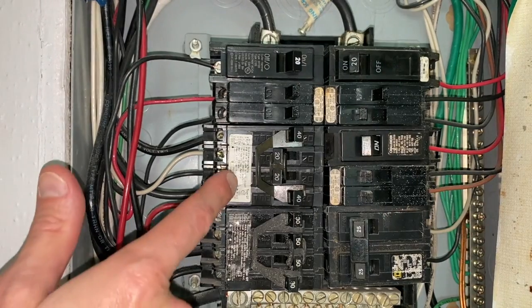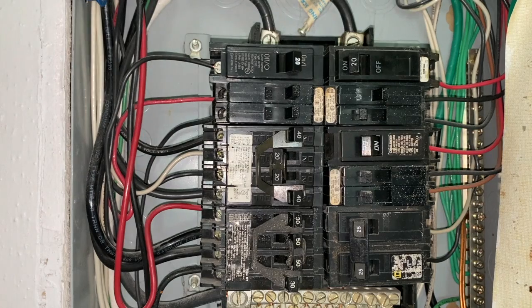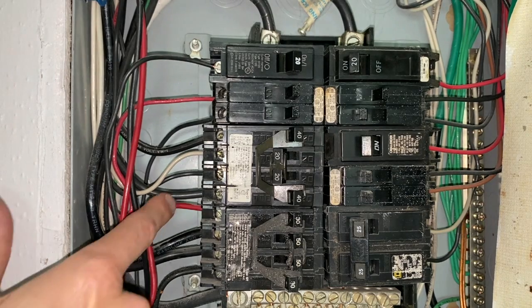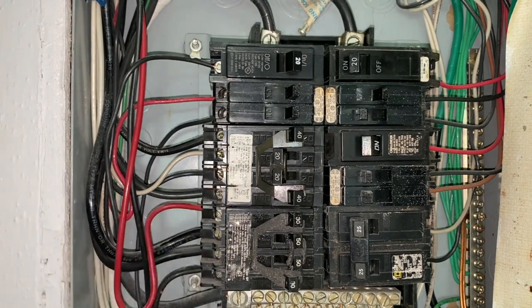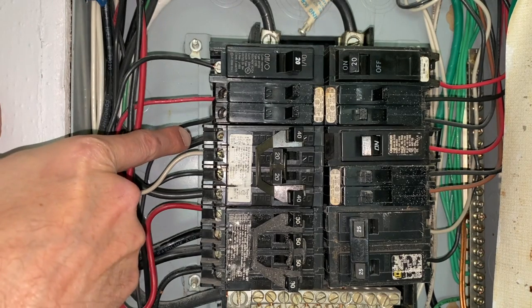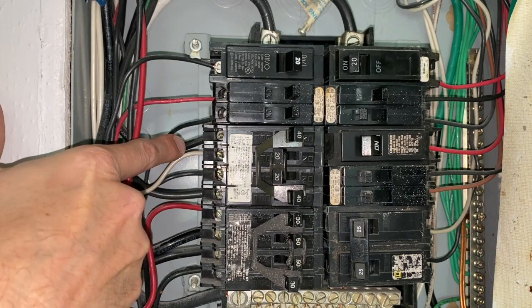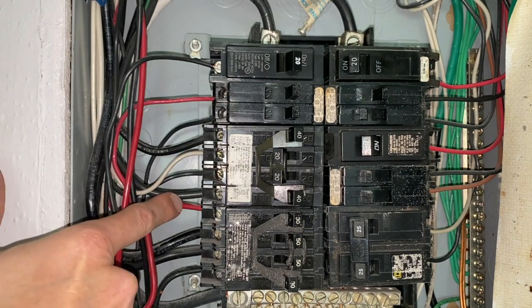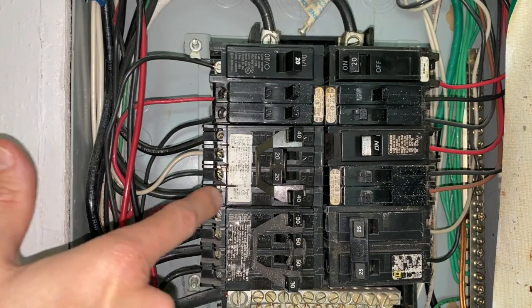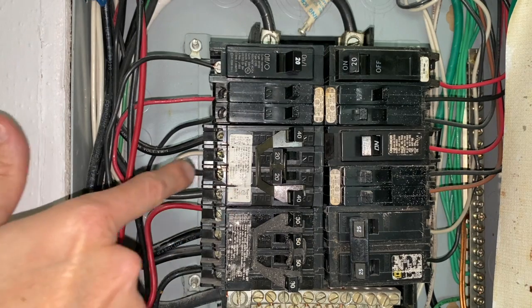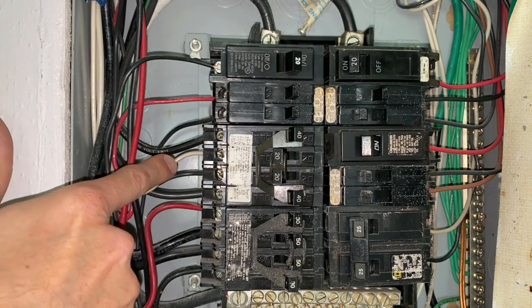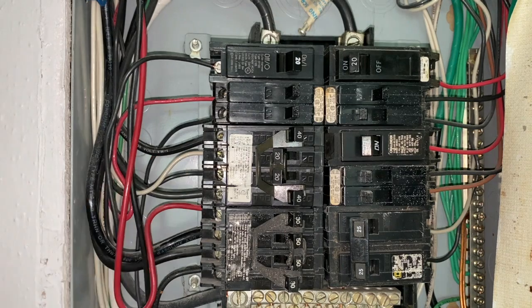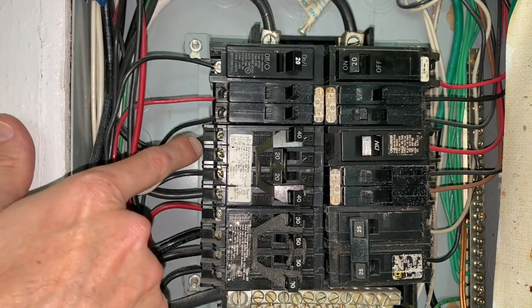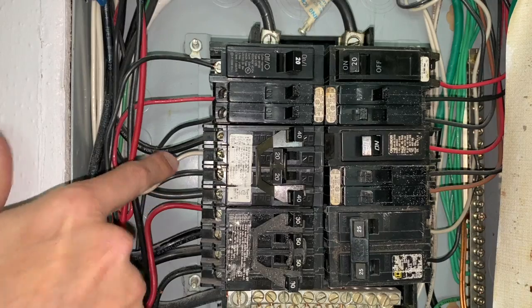Another quick reposition of the camera. At this point, it is imperative that you take photos of all of the wires that feed into your 4-pole or quad pole, quad duplex style breaker. And as you can see, going to the upper or top 40 amp, we have a thicker black wire, and coming all the way down to the bottom, that same thick black wire into the lower 40 breaker. And the two center where the 20s are, the top is a white and the wire below that is a black. So with that said, from here, I'm just going to carefully remove all of the black wires and save the white wire for last.